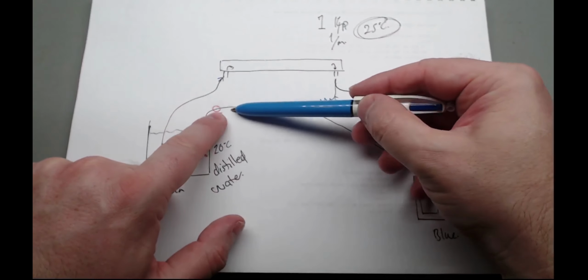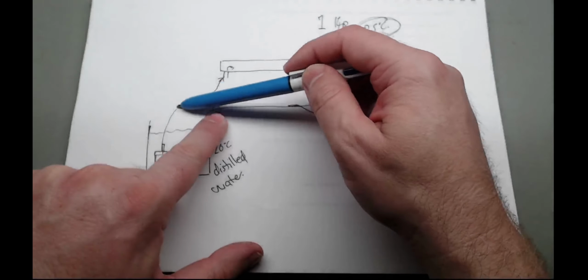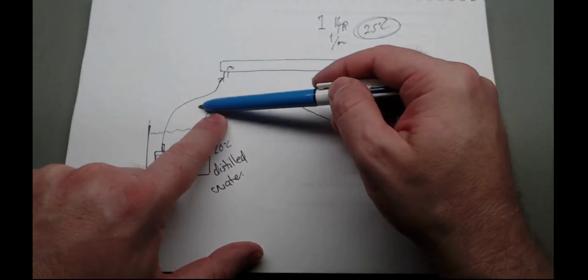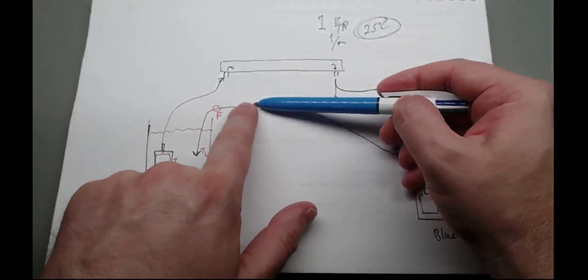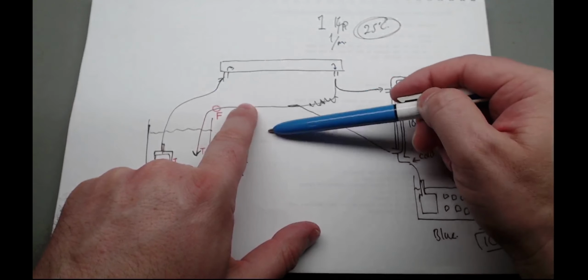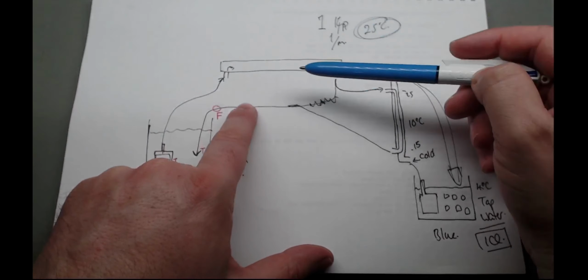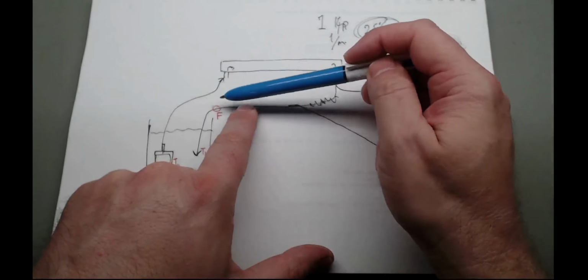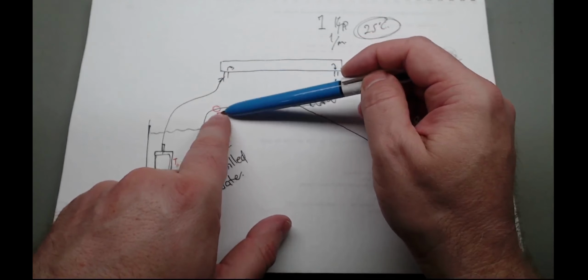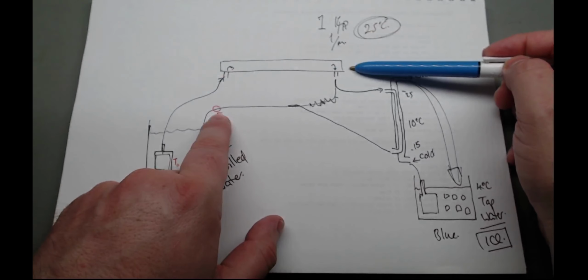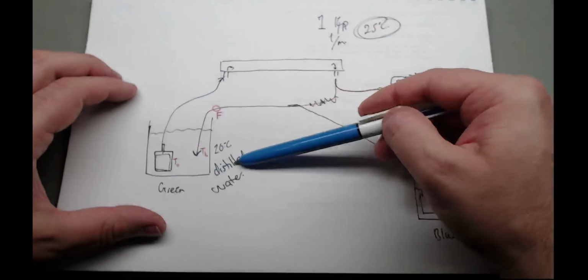So if the pipe breaks anywhere along this whole path - yes, if it snaps here, I'll just be pouring water onto the floor. I've lost 20 litres of cooling water, but the flow sensor will rapidly reach zero and it'll disable the laser. So that's what I want to do on this side.